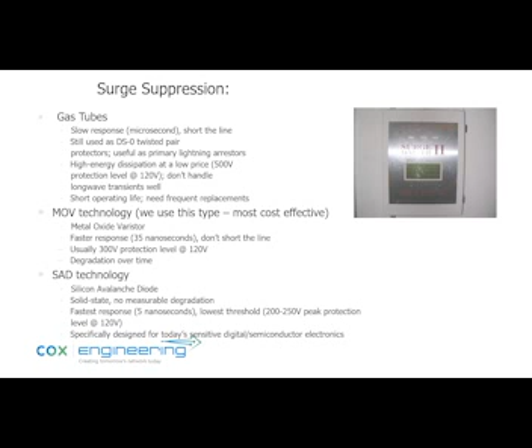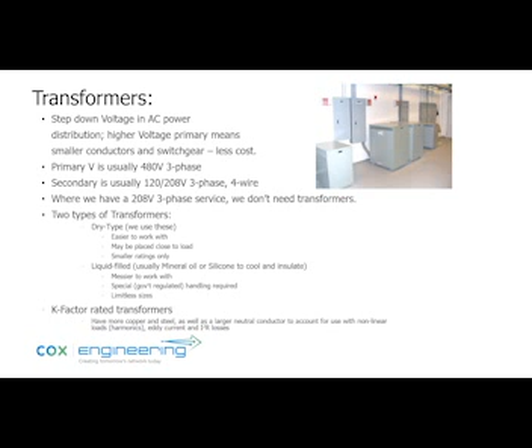Transformers basically take an AC voltage and step it up or down. Typically, it's a step down in our critical facilities. And we have dry type. These are the ones that you see here in the picture. Liquid filled, those are usually for larger and industrial applications. And then K-factor rated transformers, they have more windings and they're more robust. So when you are feeding rectifiers, it's a good idea to use those. They basically mitigate any harmonics and other losses.